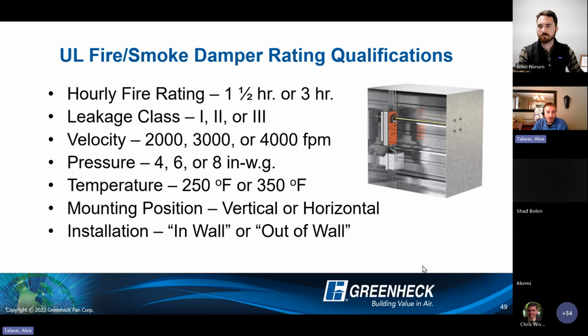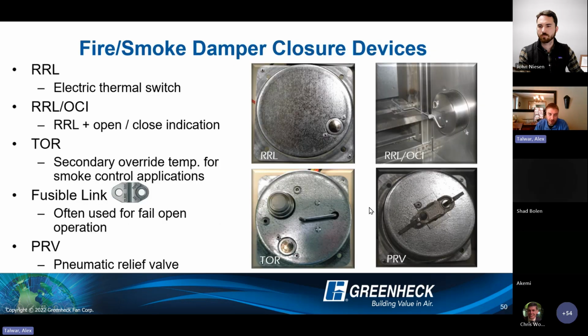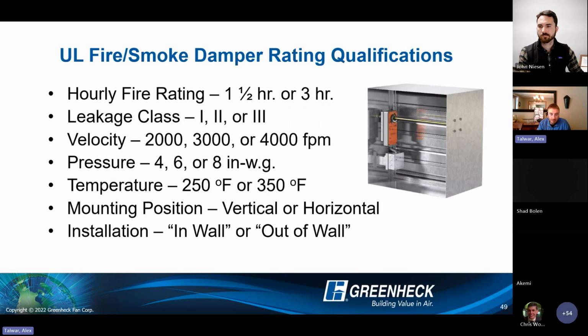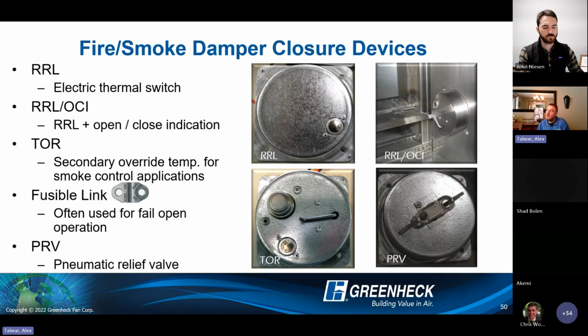All right, we will keep rocking along here with the fire smoke damper portion. So talked about the product itself, the ratings. We're going to see actuators like we did with the smoke dampers. However, now for a heat response device, the typical heat response device, instead of a fusible link, is going to be that little kind of cup that you see in the top left picture there, called the RRL, Resettable Reusable Link. Essentially, it's a little thermostat built into this cup. And then once the heat increases, gets to that 165 degrees, that thermostat pops in and cuts the power to the actuator, allows the spring return mechanism to close the damper.